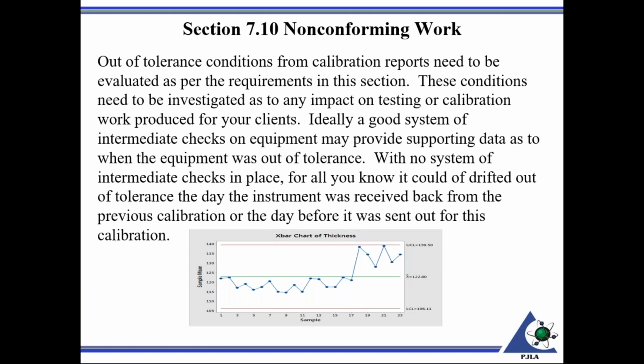So I just want to elaborate a little bit more on that. Before, if you had nothing in place at all, and it was sent out, say, on a 1 year interval, you'd have to go back that whole year. If you had a good system of intermediate checks in place, ideally, you may be able to catch when it may have drifted and perhaps cut that time down significantly. Ideally, if you really have a good system of intermediate checks and perhaps have good control limits set, then it may have been caught even before the instrument has gone out of tolerance.